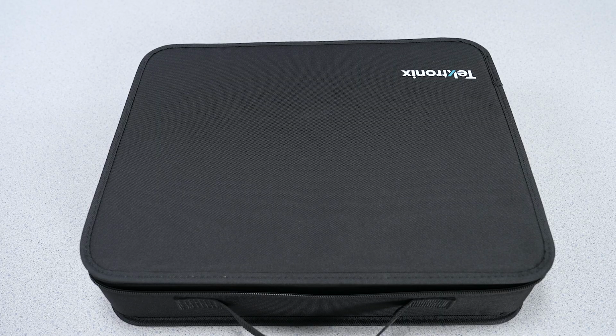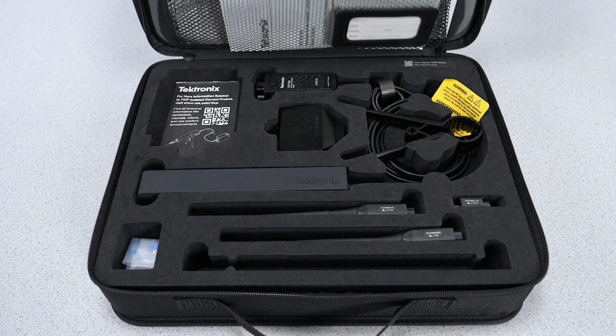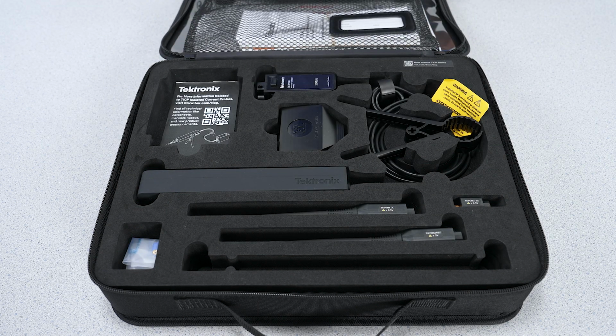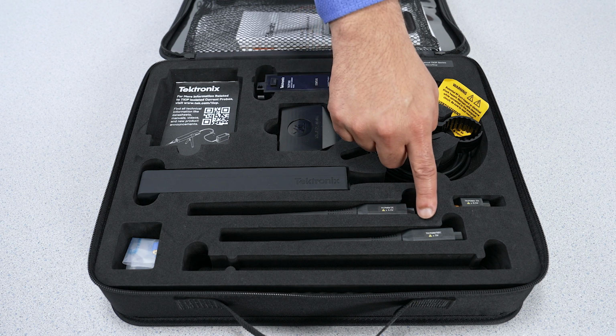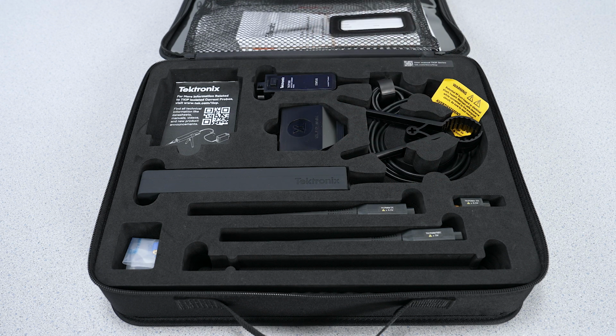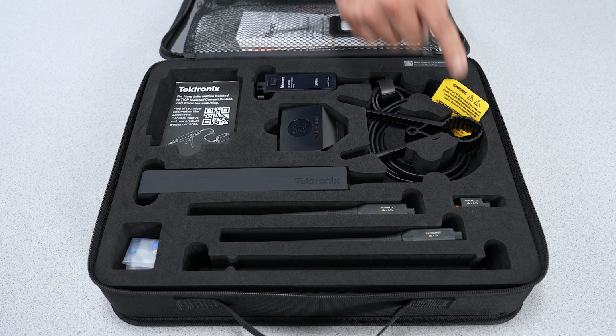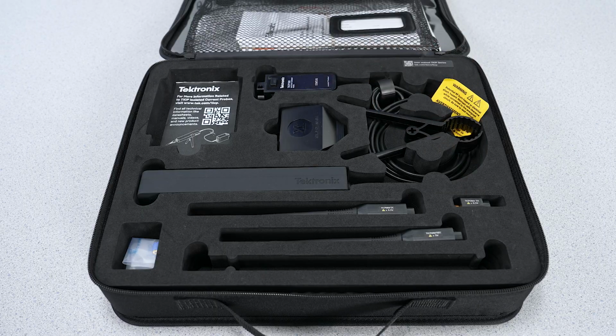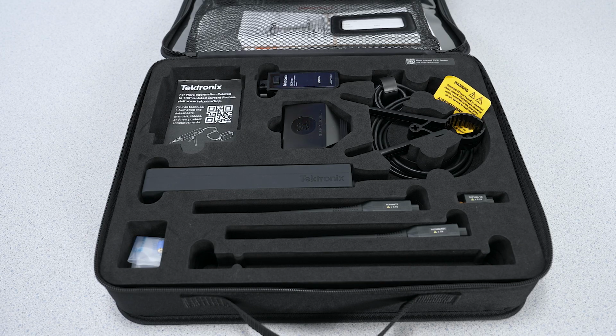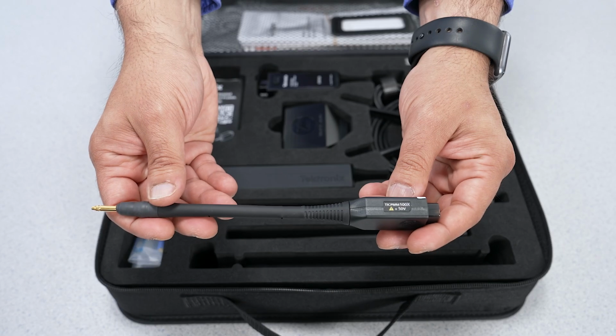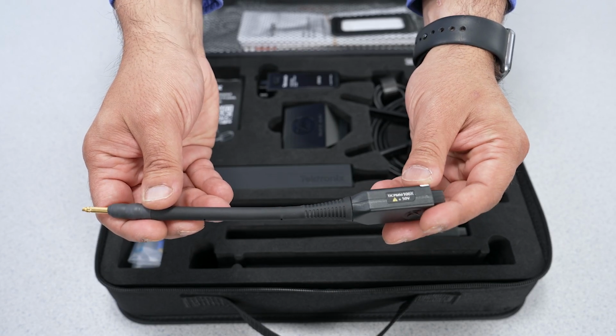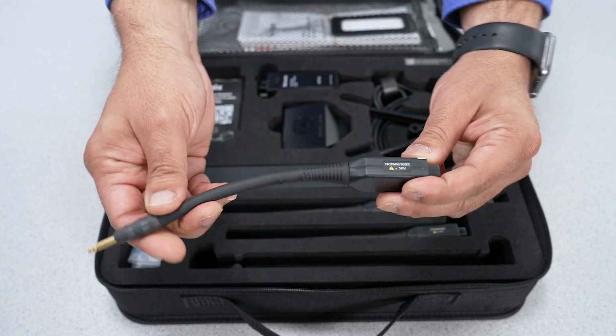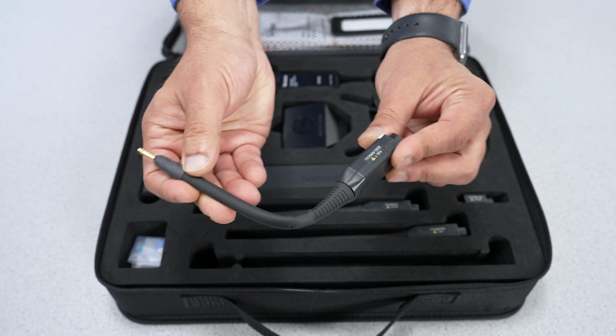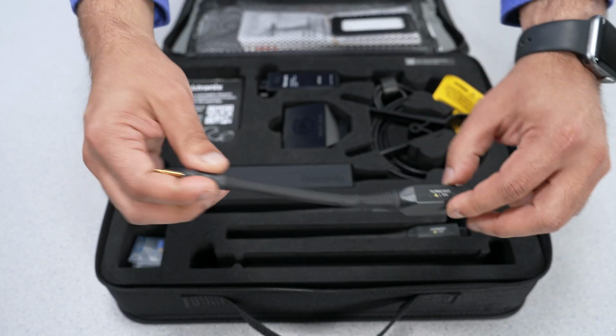To handle a wide range of current measurements, the probe comes with different attenuation tips and adapters. The 1x and 10x MMCX tips are included in the standard package along with an SMA adapter. For applications that require higher attenuation, an optional 100x tip is available. All these tips are designed for flexibility with a low bend radius to help minimize force on the DUT.